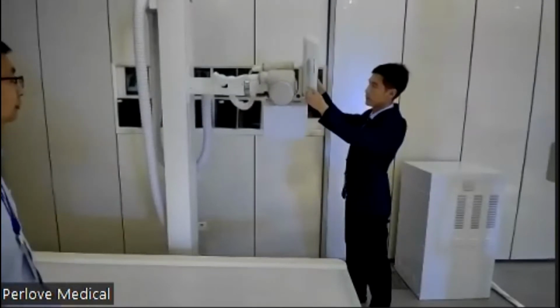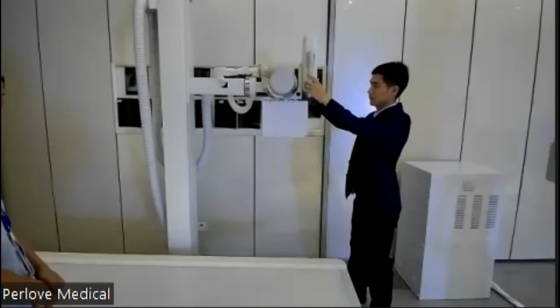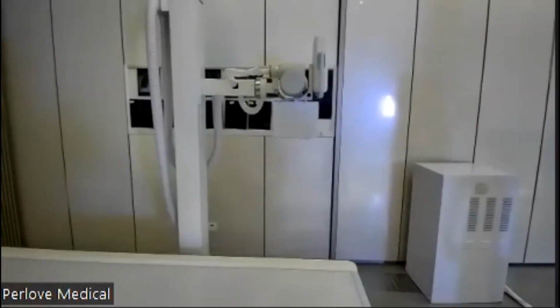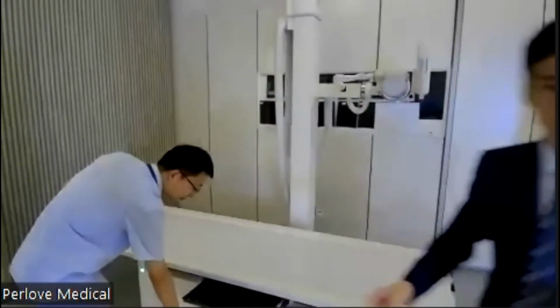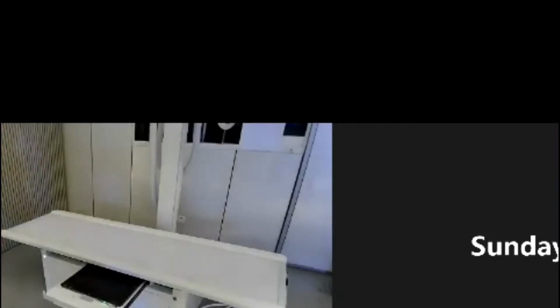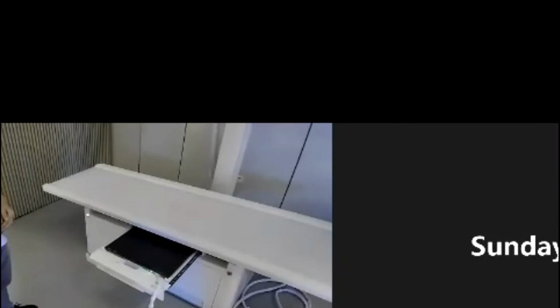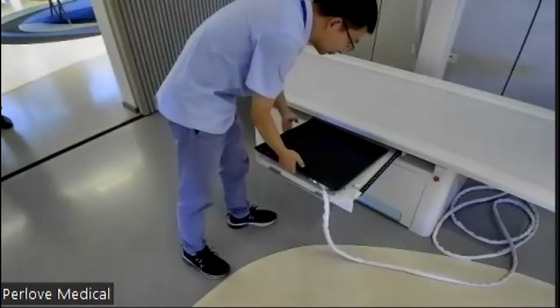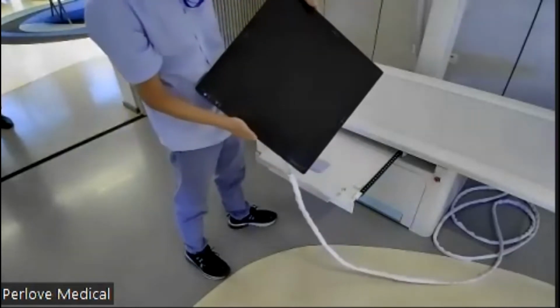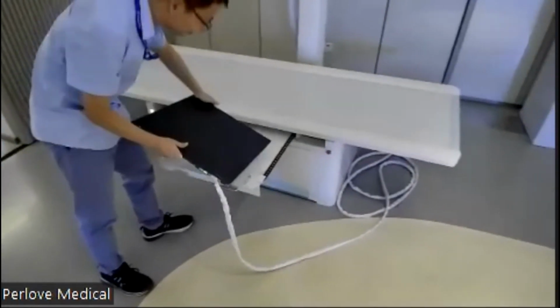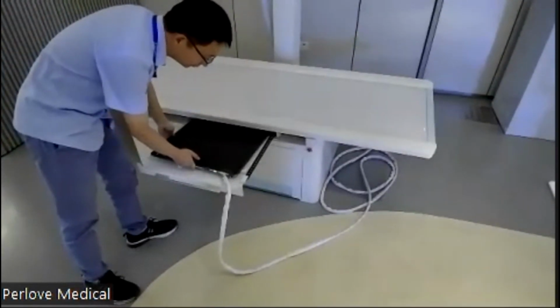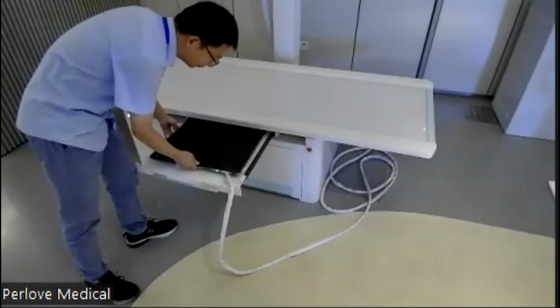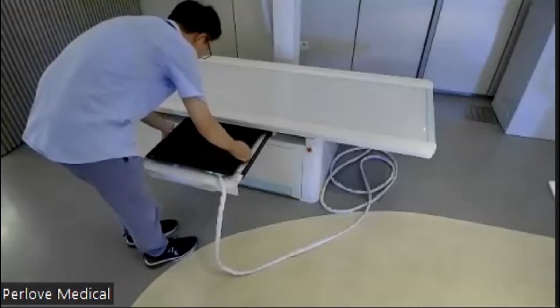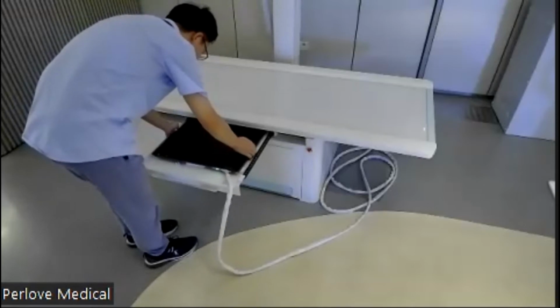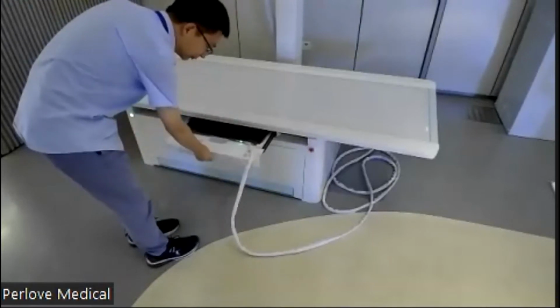You can see all the mechanical movement. And Mr. Adam will show us the flat panel detector, the dynamic flat panel detector. You can see it's portable and large size, a 17 by 17 inch dynamic flat panel detector, capable of radiography and fluoroscopy at the same time. You can use it for the patient table and also for the Bucky stand. Very convenient to remove it. And wherever you put it in the cassette, in the patient table, it will be recharged automatically. So you don't need to wait for the flat panel detector to recharge to use it.